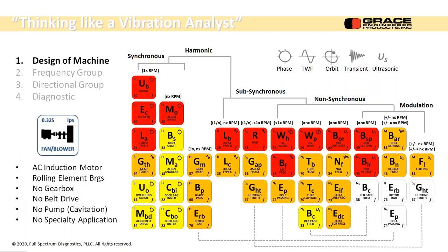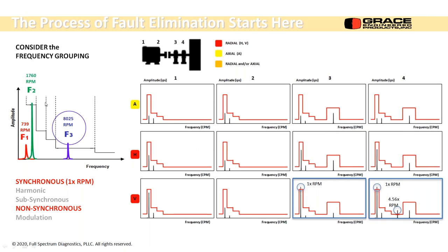The other fault, you remember we had two. We're going to walk through the same thing. So I consider the design of the machine, and we get rid of all the gearbox and belt drive and oil film bearings and DC motor problems and so forth. So we're down from 35 to, I think, 23 faults. Same as before. Now we're just looking at a different frequency.